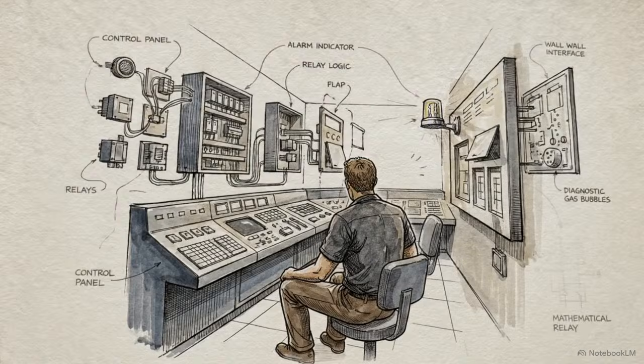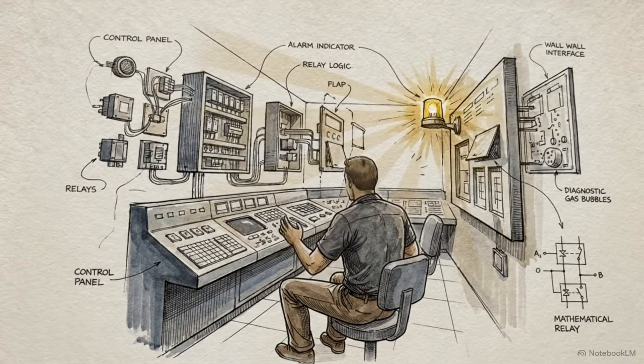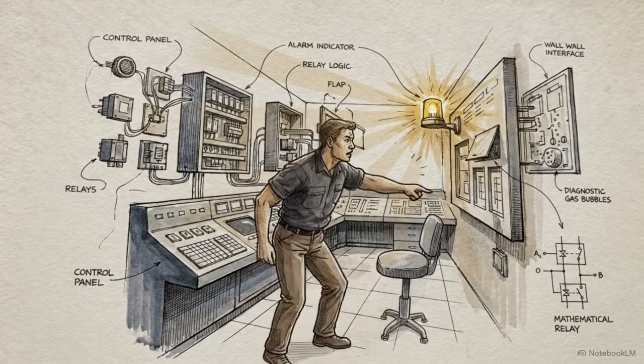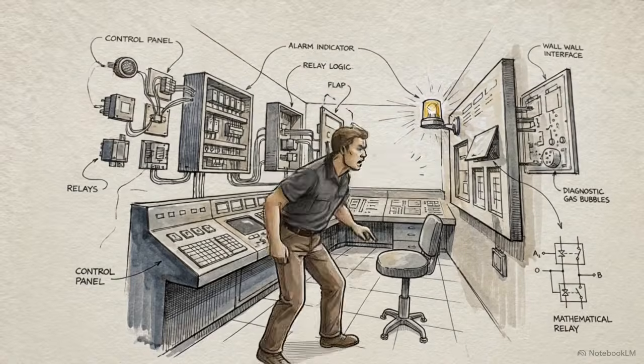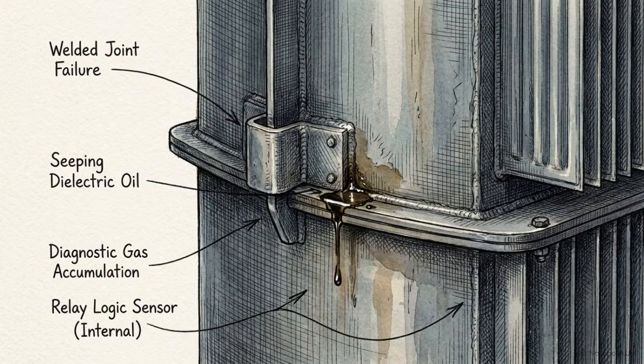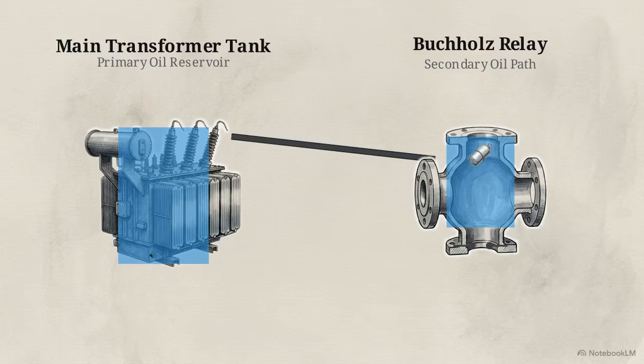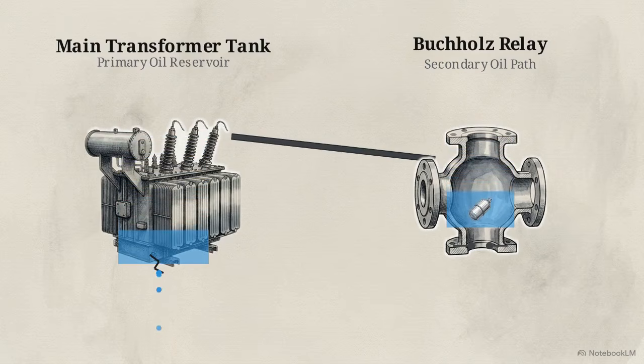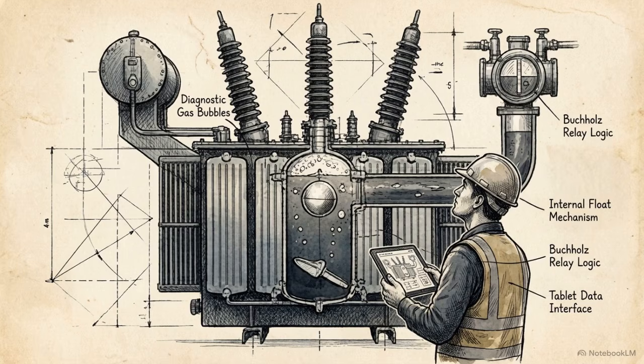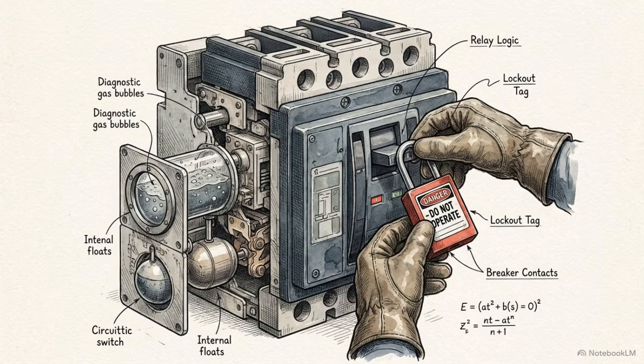This triggers an early warning alarm in the control room, alerting operators without actively disconnecting the transformer's power supply. This design also acts as a physical safety check for the oil itself. If a structural breach in the tank causes a slow oil leak, the fluid level in the relay drops, triggering this exact same float alarm. This upper float alarm circuit buys maintenance engineers critical time. It gives them a window to investigate and isolate the issue before the equipment completely fails electrically.